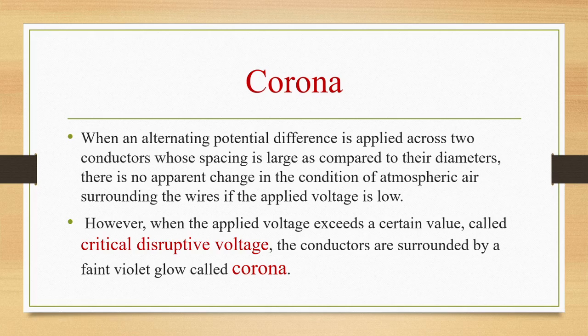If the ratio of spacing between the conductors to the radius of the conductor is less than 15, flashover will occur between the conductors before the corona phenomenon occurs. For overhead lines, this ratio is far more than this number, and hence flashover can be regarded as impossible. So what exactly is corona? Corona phenomenon is defined as a self-sustained electric discharge in which field intensified ionization is localized only over a portion of the distance between the electrodes.